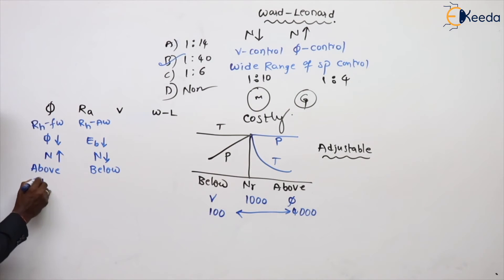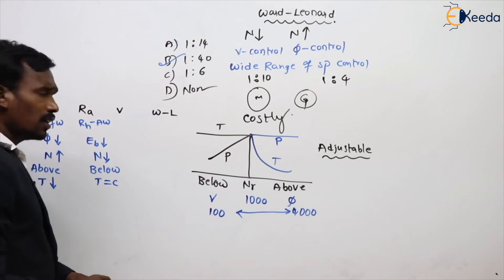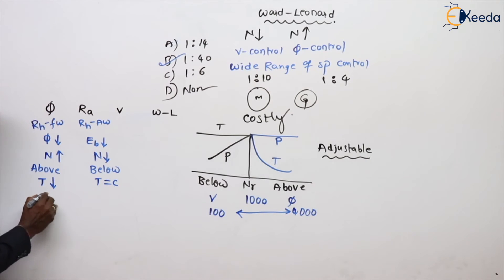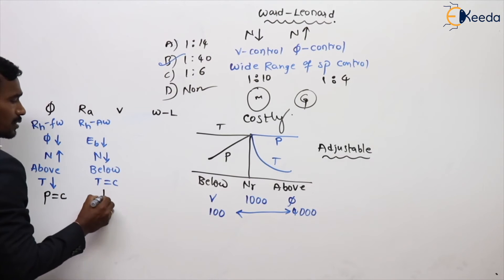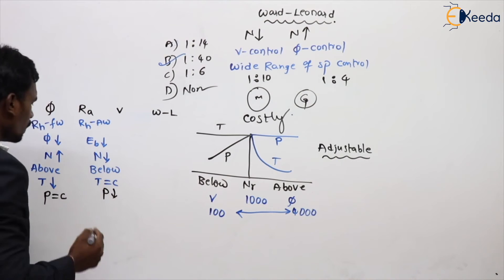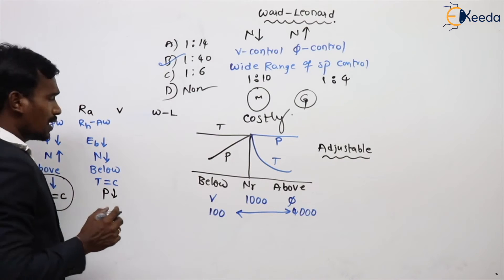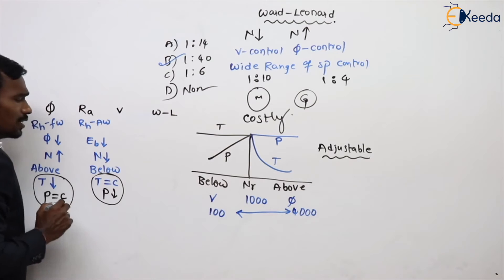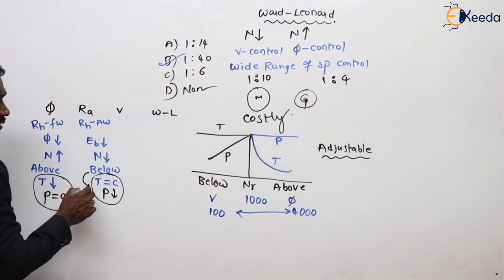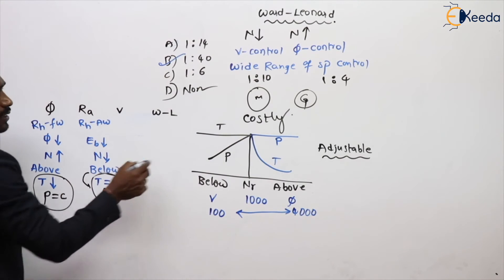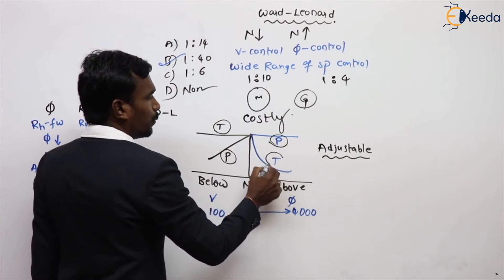In flux control, the torque is reducing while speed increases, so power is constant — constant power variable torque drive. In armature resistance control, torque is constant but when speed reduces, power also reduces — constant torque variable power drive. So, below rated speeds are constant torque variable power drive, and above rated speeds are constant power variable torque drive.